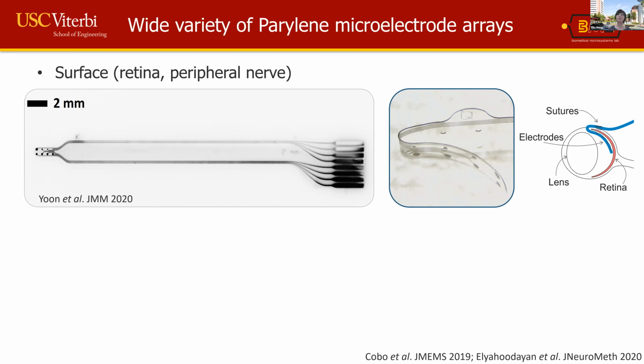And so the image here of the device on the top is a device that's intended to sit on the retina. You're looking at an as-fabricated device. The actual electrode interface is the leftmost tip here. You'll see a series of 8 different electrodes, of which there are 4 different sizes. This is an experimental array because we don't know the most appropriate size. This is intended for use for stimulation of the retina and specifically for use in the rat eye.